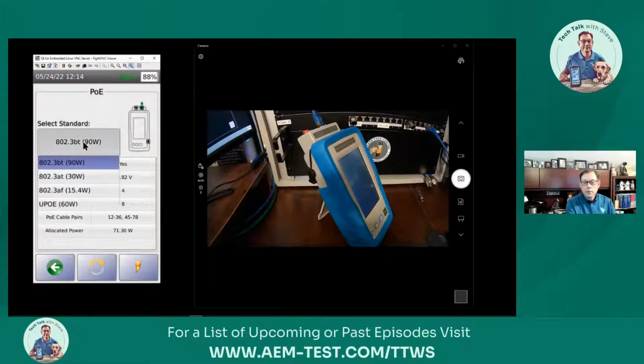One of the things you can do here is choose whether you want the 90 watt BT, the 30 watt AT, the 15.4 watt AF, or if you have UPoE, the 60 watt. We'll leave it set at 90. We've got PoE on all 4 pairs, we see the class, the type, we see our voltage. And the most important one, the very first line - if you have a 'no' here, you're not going to get any of this other information.